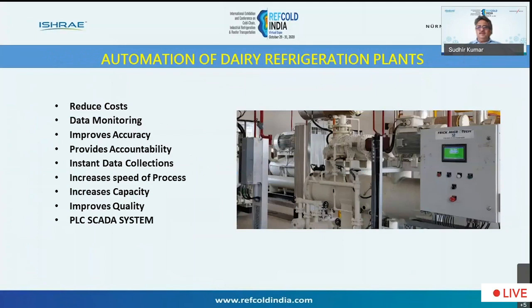And next, not last but not the least, is the important factor of automation in dairy or any refrigeration plant. See, the first and foremost is your labor cost comes down, and you can monitor the data accurately, and the improvement in the efficiency of the plant is tremendous because you are having all controls which are monitored through a PLC or a SCADA system. You can use ultimate control systems, like you can have transmitters reduce the speed by the suction pressure reduction. So this is one of the biggest innovations in the dairy field.